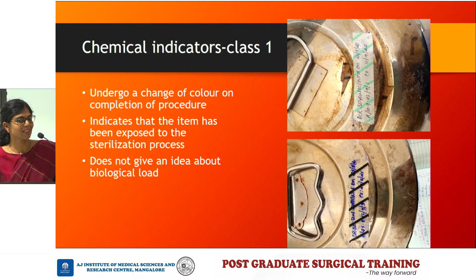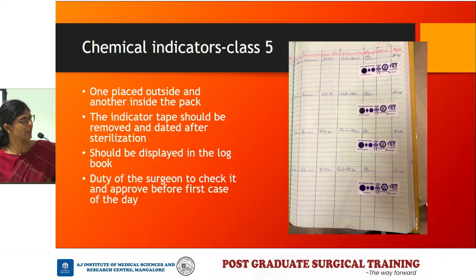So it has been exposed to the sterilization process, but it does not give you any idea about the biological load. So class 5 indicators which are placed inside the bin, inside the set are more important, and they should be removed and dated after sterilization and displayed in the logbook, and the surgeon needs to look at this and sign before the first case of the day.